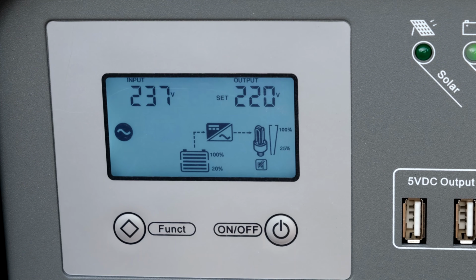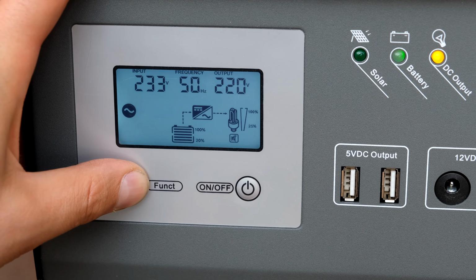In the case of a supply which is unstable, like the one I showed with the generator, you can force the inverter to run off battery, but then it kind of defeats the point because you're using the generator to feed the inverter, but you're actually using the battery. Nevertheless, if you need to, you can run it off battery even if there is an AC supply at the mains. For normal operation, you'd want this in mode 1.